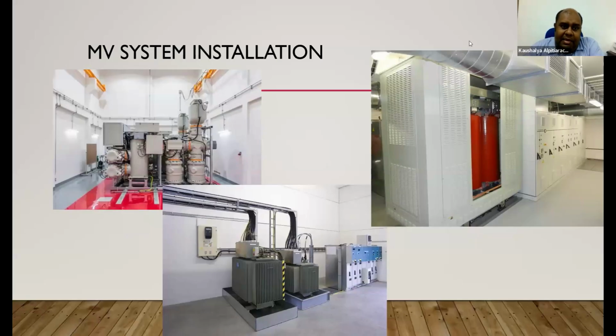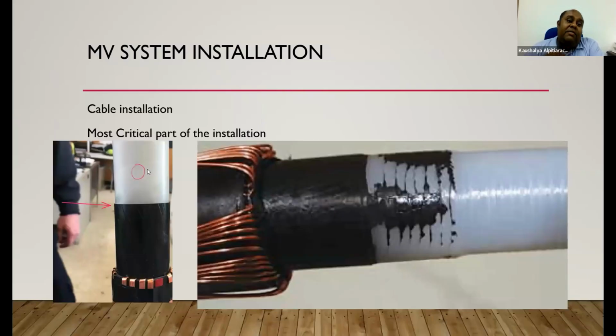Yes, this is the first image. This image shows you an SF6 insulated, maybe 30 kV distribution, and the floor is an anti-static epoxy-based floor and a gloss floor. And here, indoor installation with oil immersed transformers with catch pits, and there should be drain pits, which we don't see here. And again, anti-static floor with mat formation, another anti-static floor with mat formation. So if you maintain the environment like this, then you definitely will have the right pollution degree inside, and your lifespan and your troubles will be very less, and the reliability will be high.